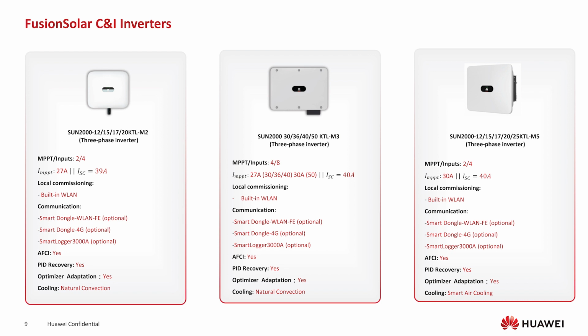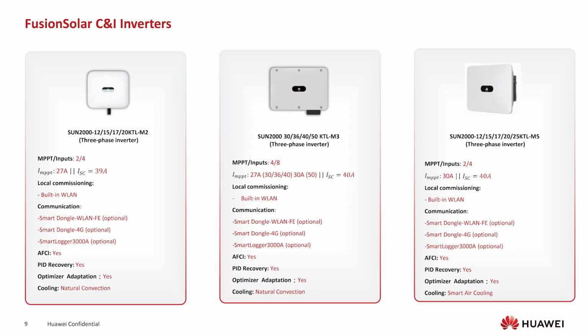Then you have the 30, 36, 40, and 50 kilowatt. It's got 4 MPPTs with 2 inputs each, so you can connect 8 strings. It's got 27 amps, and also 40 amps short circuit current. Built-in WLAN, again with all the accessories on the dongles. Also AFCI, PID, optimizer ready, and natural cooling as well.